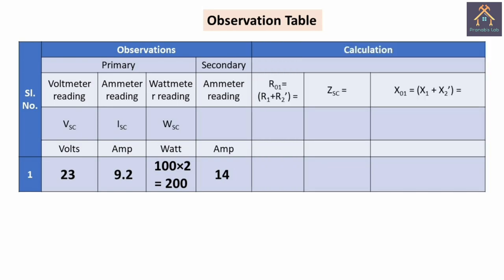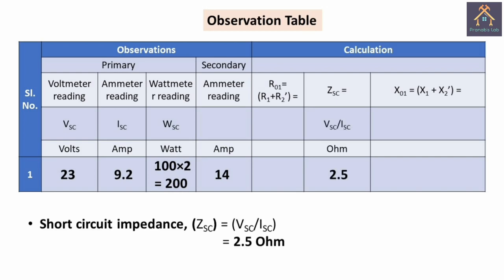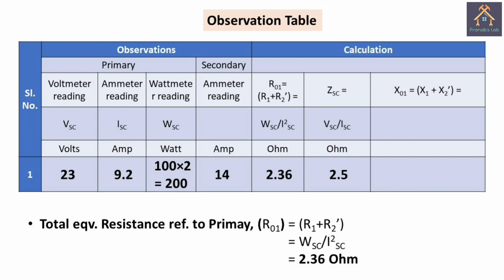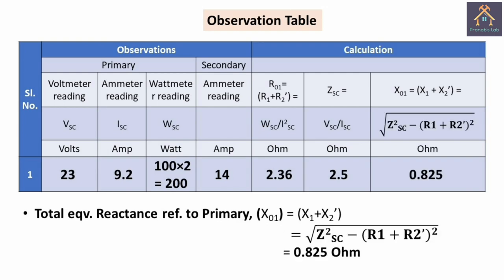Now using this data, we have to calculate the total resistance referred to primary (R01), the total short circuit impedance (Z01 or ZSC), and the total reactance referred to primary (X01). By dividing the primary voltage VSC by the primary current ISC, we can easily calculate the short circuit impedance, which is 2.5 ohm. To calculate the total equivalent resistance referred to primary, we divide the wattmeter reading by the square of the ammeter reading, giving 2.36 ohm. From the short circuit impedance and total resistance referred to primary, we can calculate X01 — the total equivalent reactance referred to primary — which is 0.825 ohm.